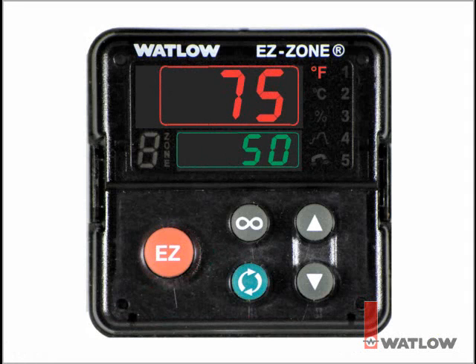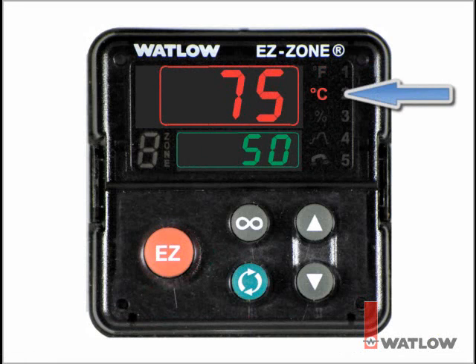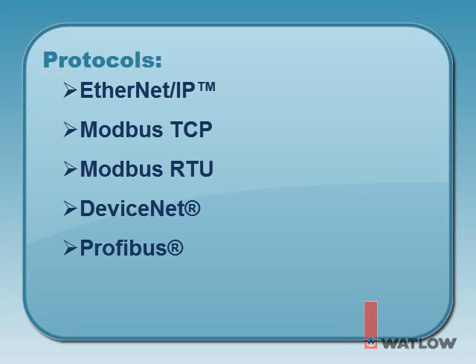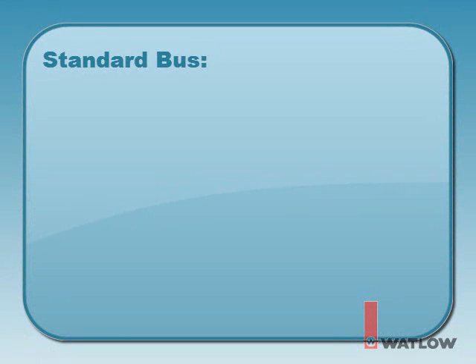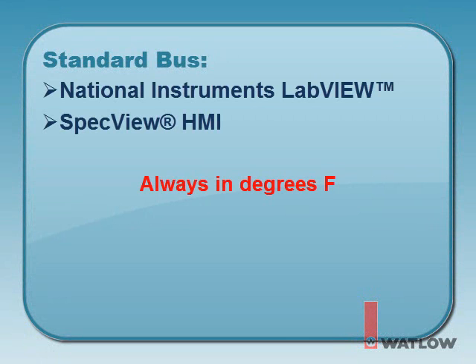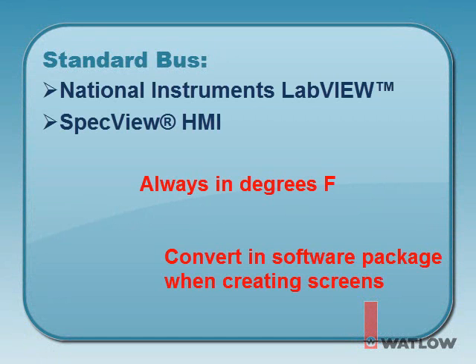EZ-ZONE models with a seven-segment display may be set to display temperature-related information in degrees Fahrenheit or Celsius. Models utilizing serial or Ethernet protocols may be set independently to transfer temperature-related information in degrees Fahrenheit or Celsius. Models utilizing the standard bus serial communications — communicating to National Instruments LabVIEW or the SpecVIEW HMI software — will always transfer temperature-related information in degrees Fahrenheit. These software packages have means within them to perform temperature conversion if required.